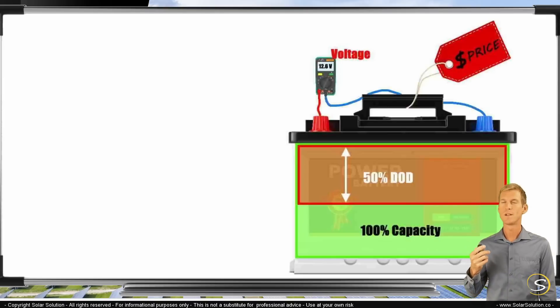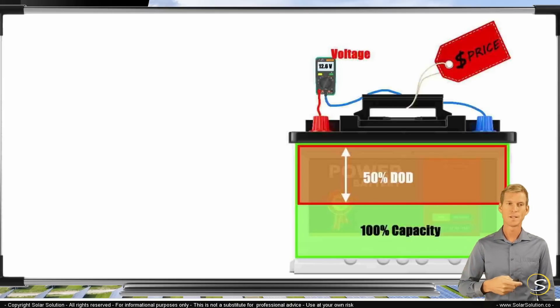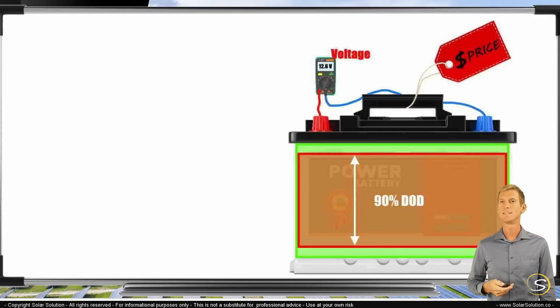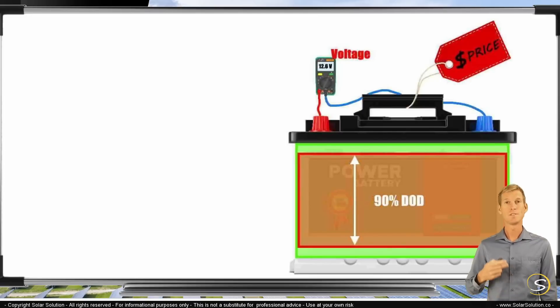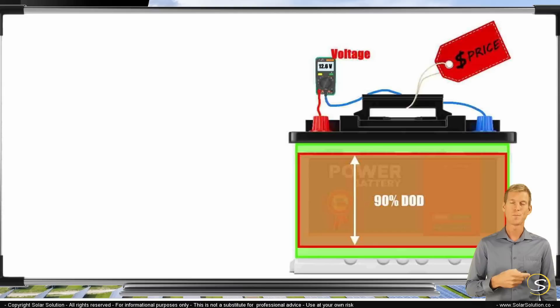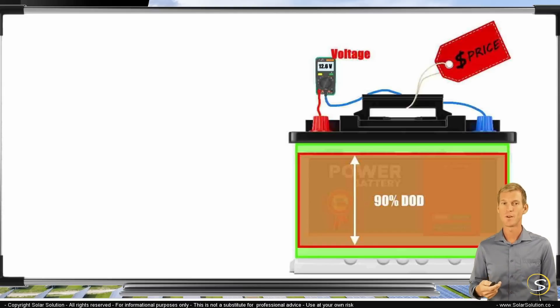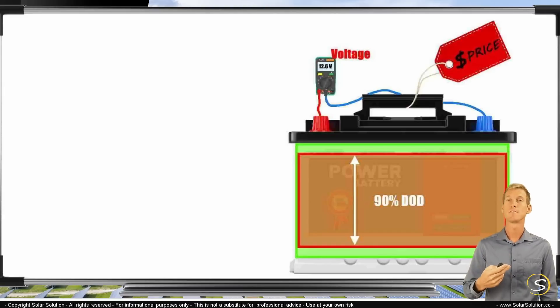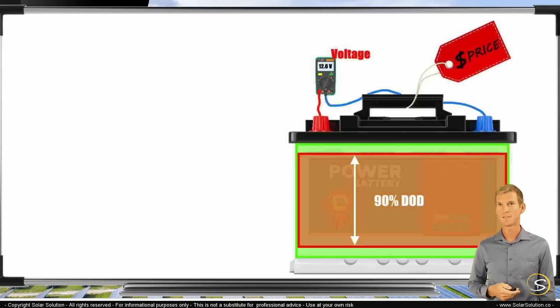As I mentioned before, lithium batteries allow us to use almost all their capacity — normally up to 90% or 95%, which is a great advantage of lithium. So you pay a lot more for the battery, but you can use much more of the capacity without negatively impacting the expected lifetime.